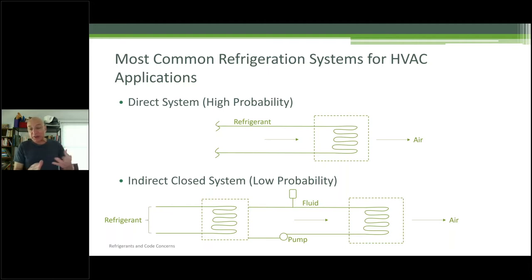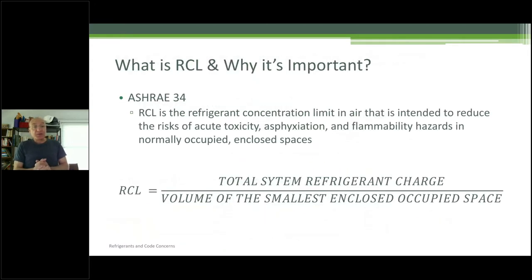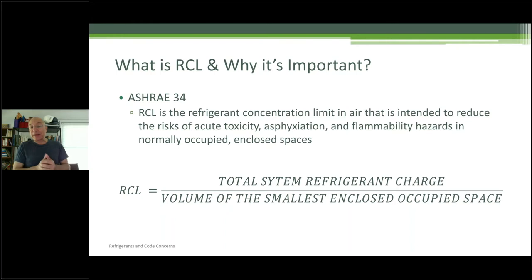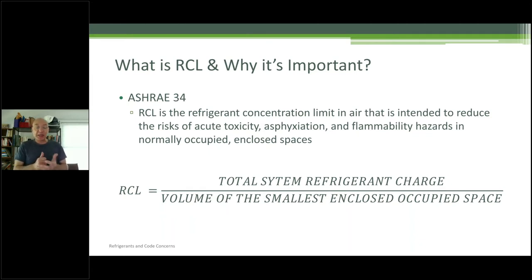As a designer, all these things come into play. What is RCL and why is it important? The refrigerant concentration limit is the limit in the air intended to reduce the risk of acute toxicity, asphyxiation, and flammability hazards in normally occupied enclosed spaces. Very simple formula: it's the total system refrigerant charge over the volume of the smallest enclosed occupied space. For those who design VRF systems, this is important.